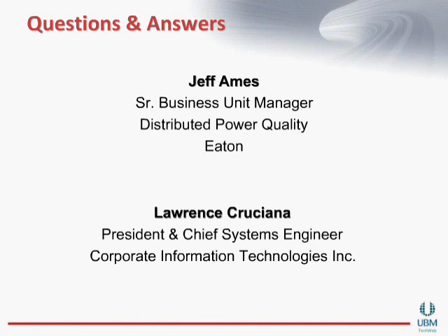Basically, the way that gets deployed is your power infrastructure device, let's say a UPS or a power distribution unit, ends up being serially connected into a localized server or workstation. As long as that server, workstation, or PC is connected to that power device serially or by USB, the IP address of the compute device it's attached to will come through and be brought into the Intelligent Power Management System.